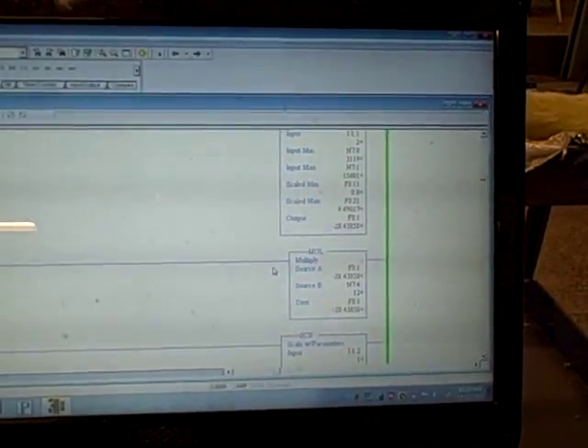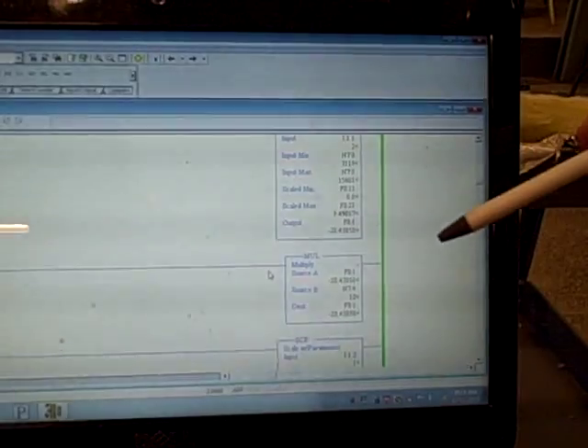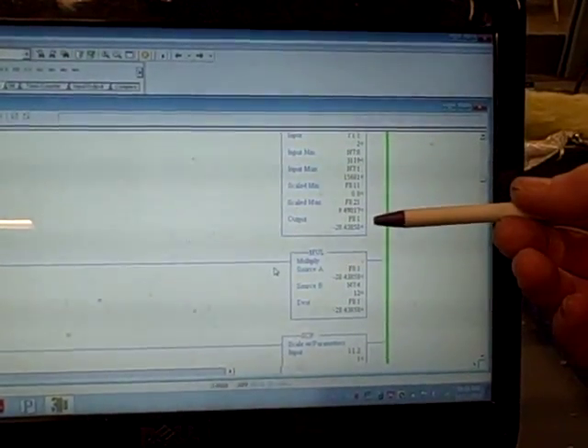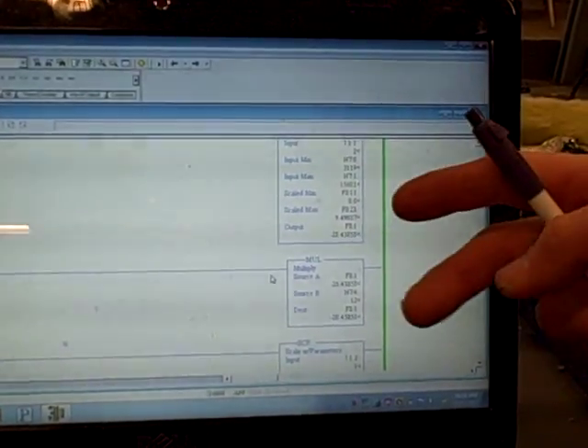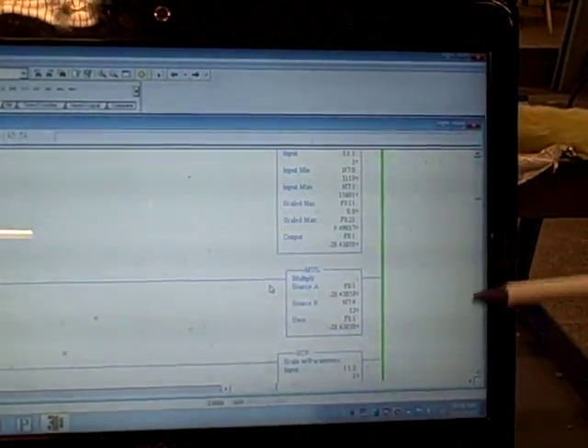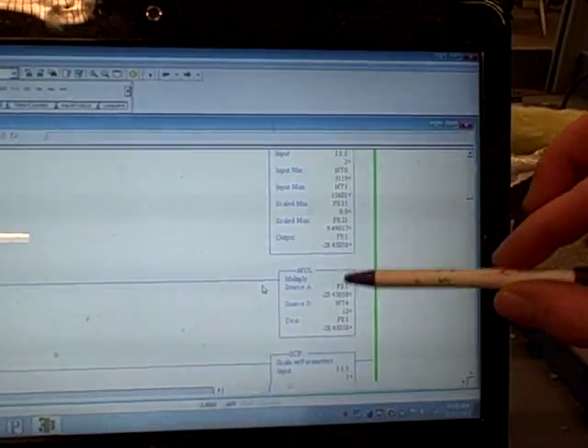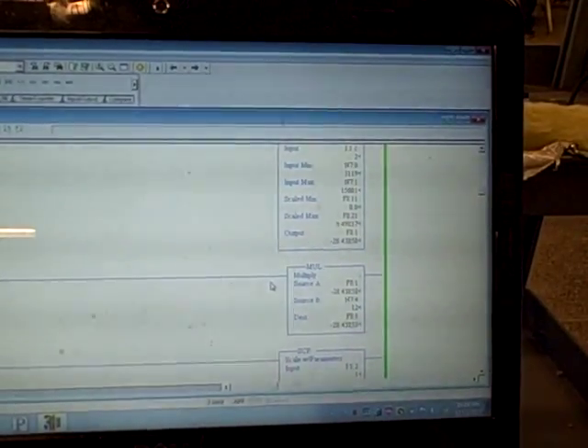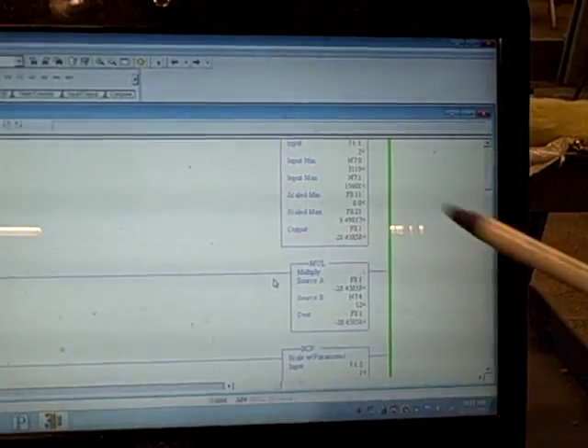You don't see the intermediate values because of the way the laptop communicates with the PLC — it does not communicate in real time, line by line through the scan. It communicates after the entire program has been scanned. The program does its job: it calculates F8:1 via the SCP instruction, then multiplies and puts the result back in F8:1, so F8:1 actually has two different values at different points in execution. But none of that gets communicated to the laptop until after the scan is done and the PLC handles its communication overhead. So the RSLogix software takes the value it read for F8:1 and displays that same value everywhere it sees F8:1 — which is not what's actually happening in real execution. Beware: things like this can make a program look wrong when it's actually doing exactly what it should.